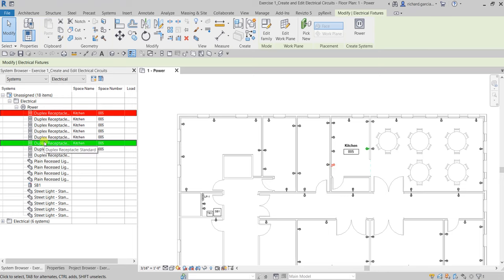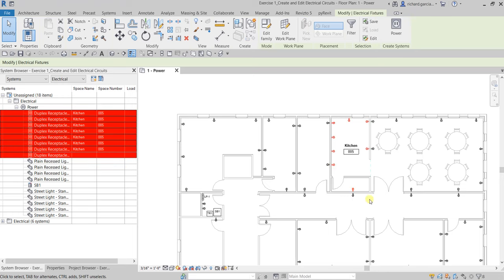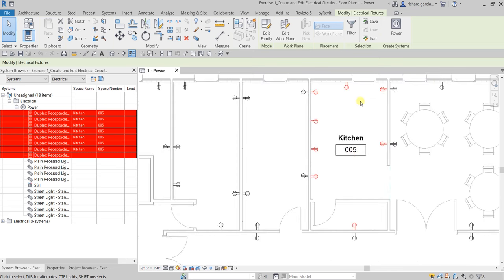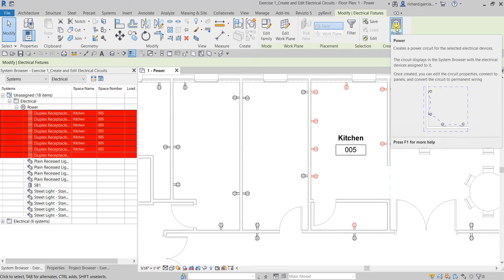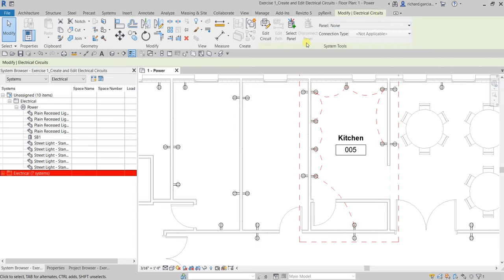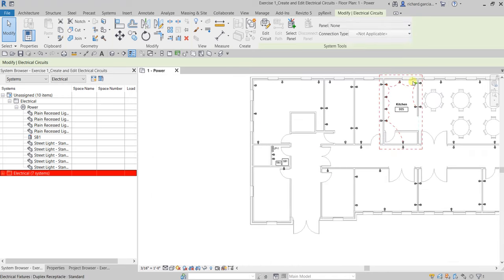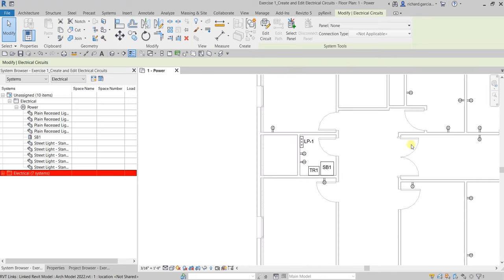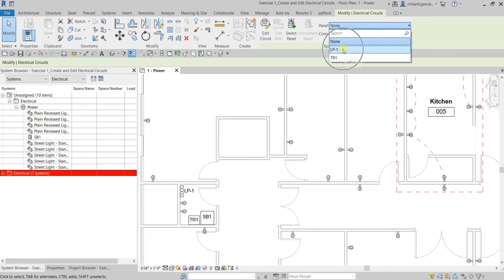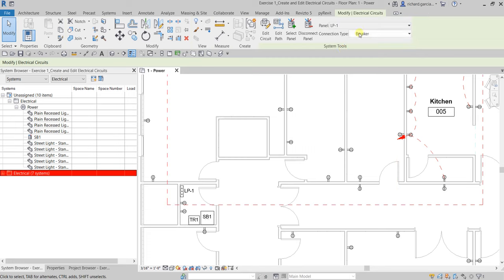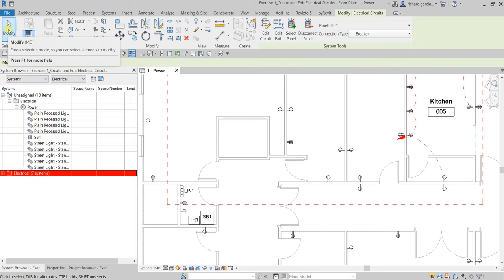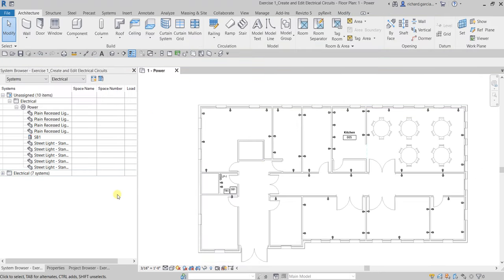I'll hold Shift and select the other receptacles to create a circuit for my kitchen area. After selecting your fixtures, look for 'Create Systems' and click Power to create the circuit. Then assign the panel — I'll connect this circuit to LP1 by clicking the drop-down arrow and selecting LP1, then click Modify to deselect.